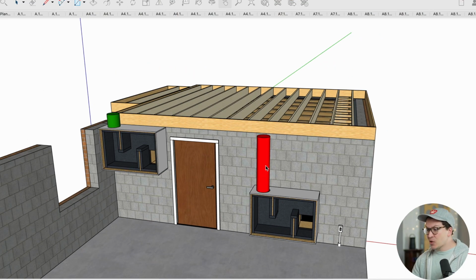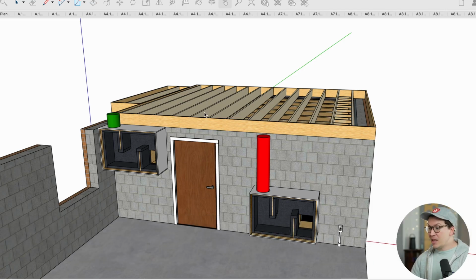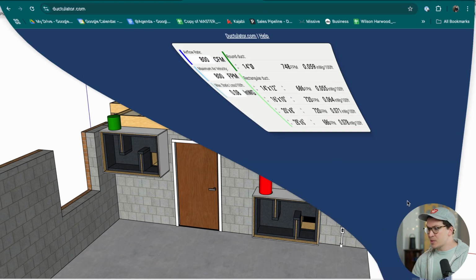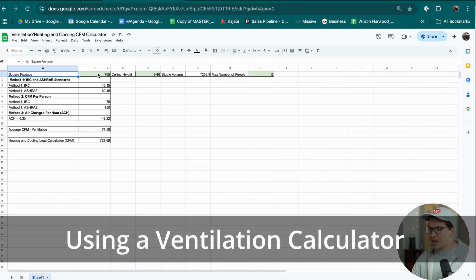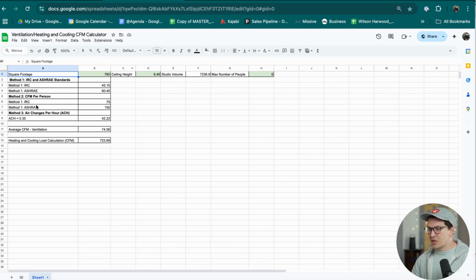In this case, though, we actually have the air handler for the entire house going into this system. So what I do is I figure out the number of air changes per hour that I need for heating and cooling loads in the room that I'm trying to heat or cool. And for that, we need to go into some special calculators. So here is a calculator I created for my designs. It's called my Ventilation, Heating, and Cooling CFM calculator. And it takes into account some of the air changes per hour for just ventilation. But for this situation, we're going to look down here and put in the total square footage and the ceiling height of our studio. And that's going to give us the CFM, the cubic feet per minute of air needed for 6 air changes per hour, which is to code for heating and cooling load calculations in our system.